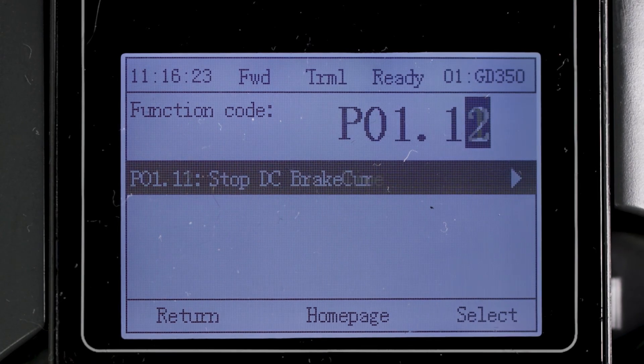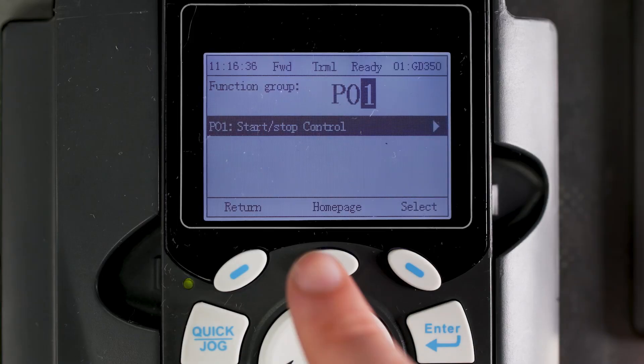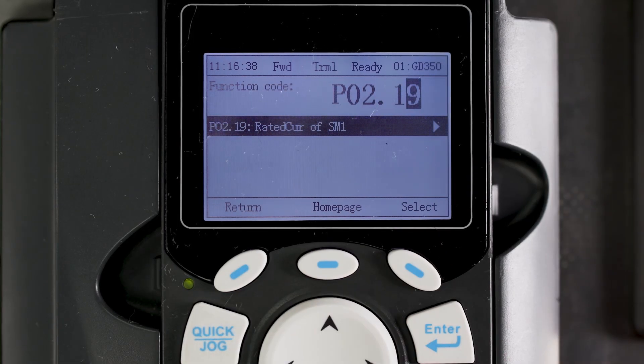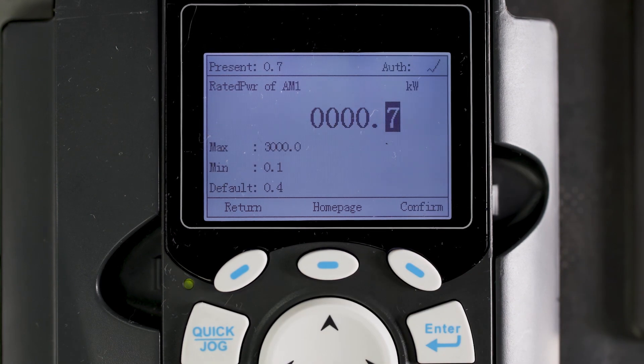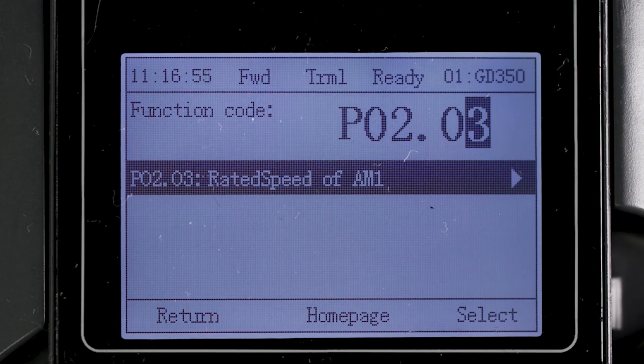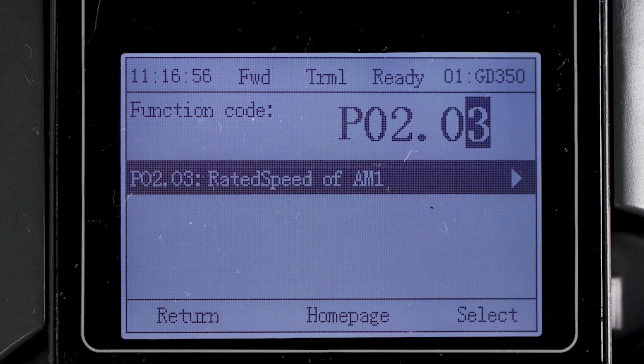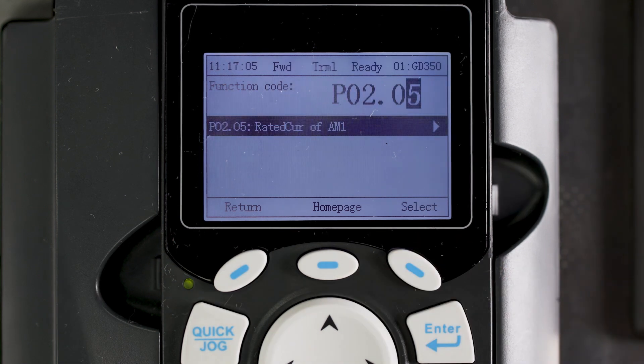.18 could be enabled to allow the drive to start automatically in the event of a power outage. The P02 group is the parameters of the motor. You will need the motor nameplate information during this process. .01 sets the kilowatt rating of the motor — don't confuse that with the horsepower rating. .02 sets the motor's rated Hertz. .03 sets the motor's rated speed. .04 sets the motor's rated voltage, and .05 sets the motor's rated current and amperage.